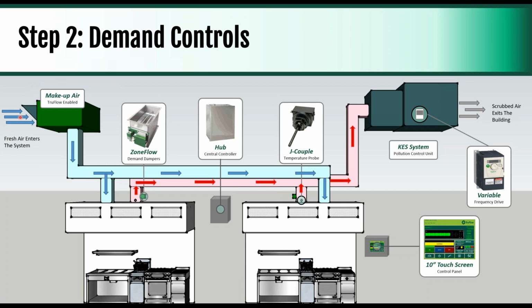Makeup air is actually one of the biggest places where energy is saved, just because if you're exhausting less air, you're tempering less air coming in. So you're heating and cooling it less, which is one of the bigger costs for commercial kitchens. One of the reasons that energy savings are so important in commercial kitchens is that typically in buildings, the kitchen is the #1 source of energy consumption, and kitchen ventilation is either #1 or #2, depending on the size of the walk-in cooler and things that they've got going on. So it's an energy hog, and so we really try to take steps to minimize the energy consumption as best as possible.